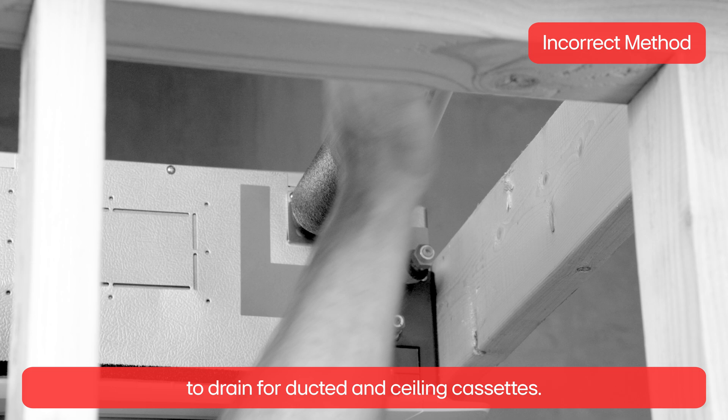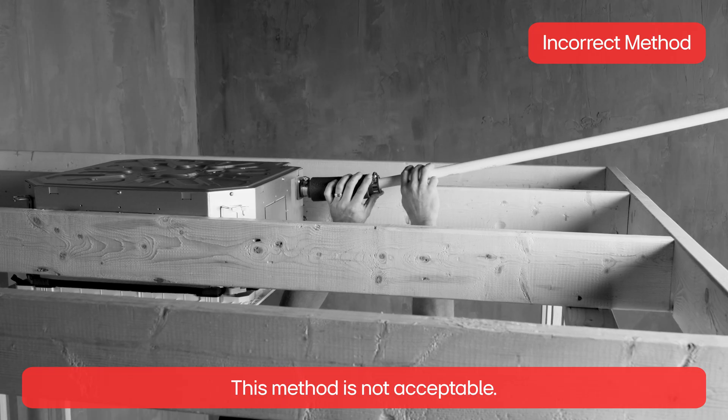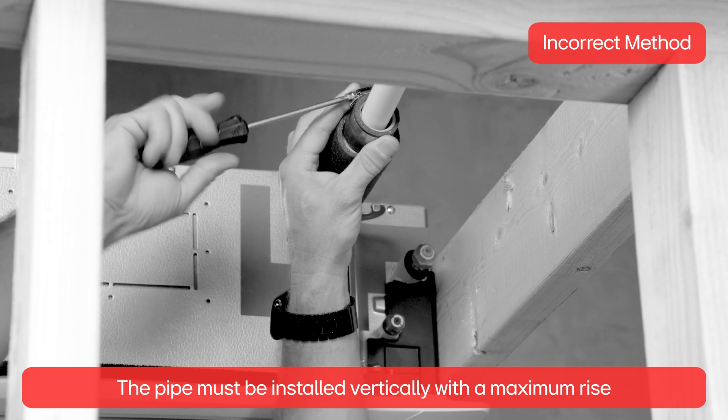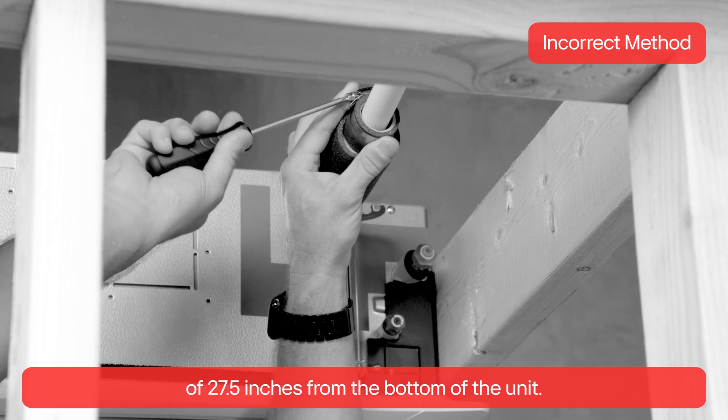Now, we will demonstrate a common but incorrect attempt to drain for ducted and ceiling cassettes. This method is not acceptable. The pipe must be installed vertically with a maximum rise of 27.5 inches from the bottom of the unit.